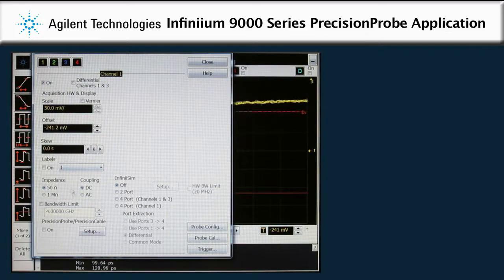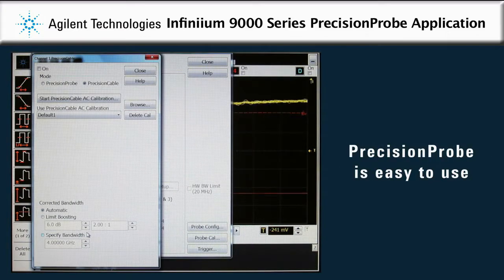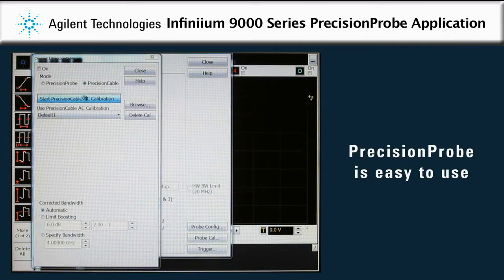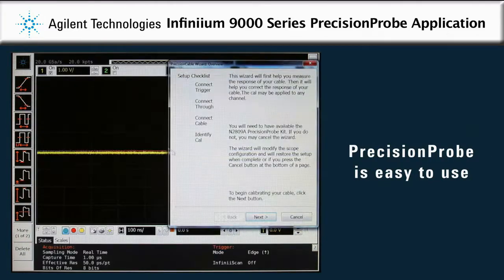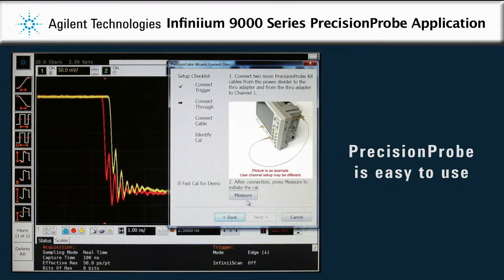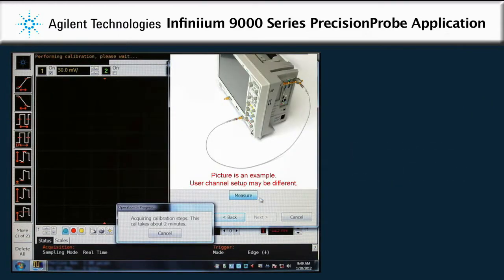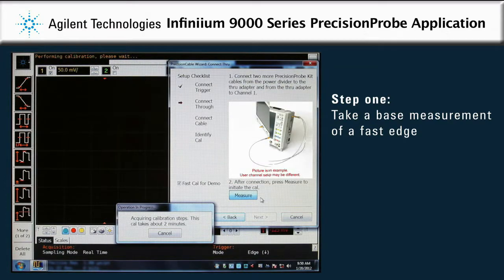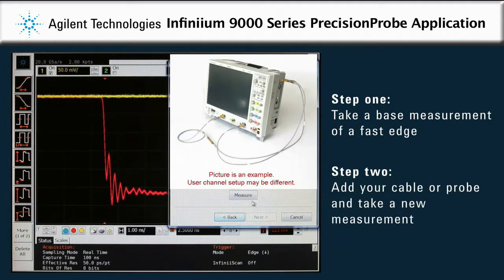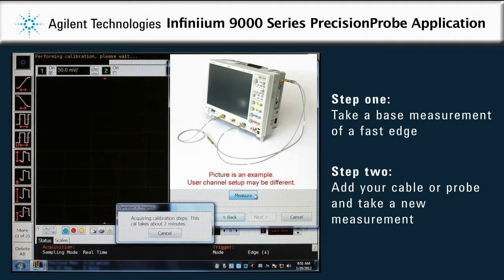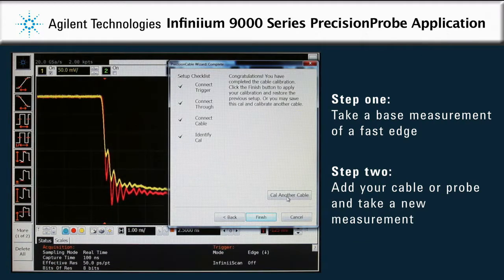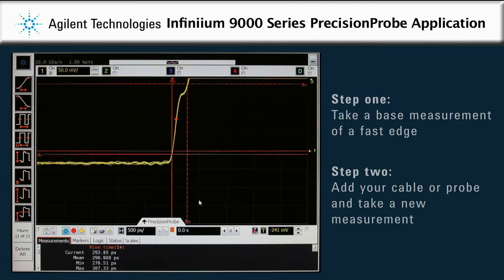In this example, see how easily Agilent's precision probe application removes measurement inaccuracies from a BNC cable. First, take a base measurement of a fast edge that's built right into the scope. Second, add the cable to the measurement path and take a new measurement. Precision probe then calculates the transform function to apply to the second measurement with the cable to make the measurement identical to the initial base measurement.